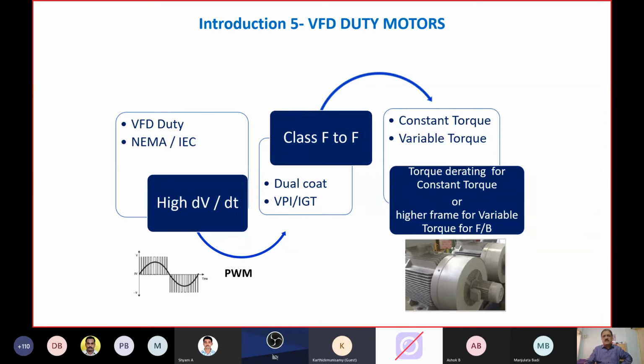I have one slide just as a commentary again, where when a motor is used for a VFD application, the motor should qualify as a VFD duty motor. It should not be simply used with a VFD, and the stress in the insulation or winding wire should not lead to failure of the motor because of the VFD. Therefore, the minimum requirement that a motor has to have to meet VFD duty is using dual coat winding wire, class F insulation, class F varnish, and also class SF insulating papers.